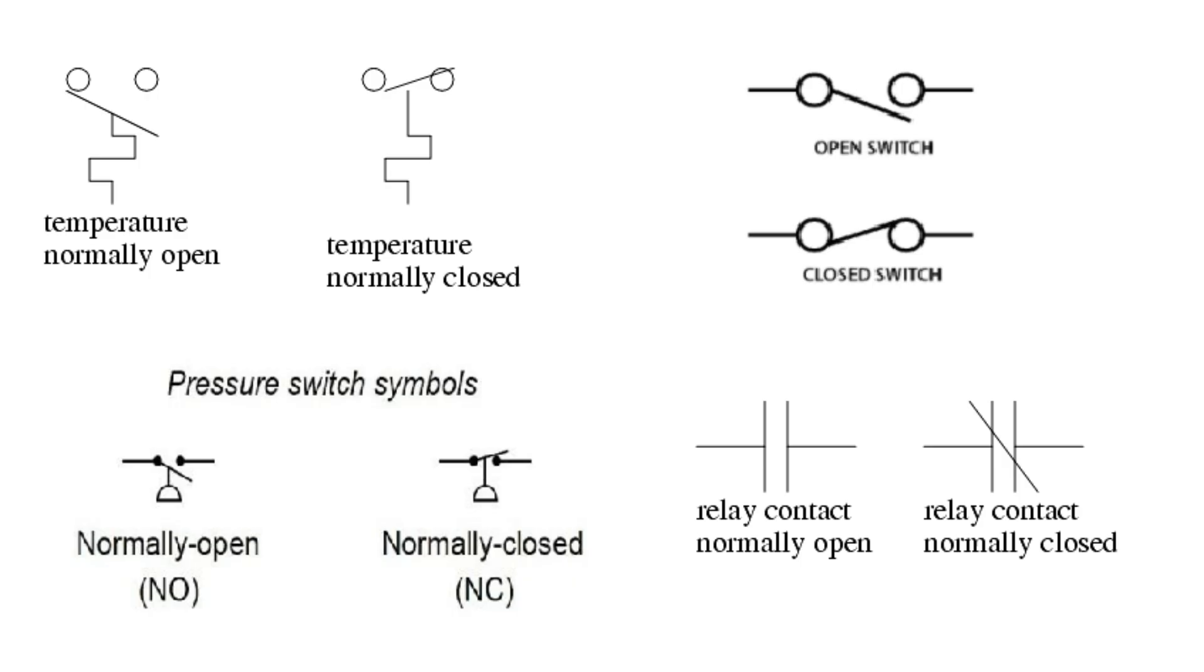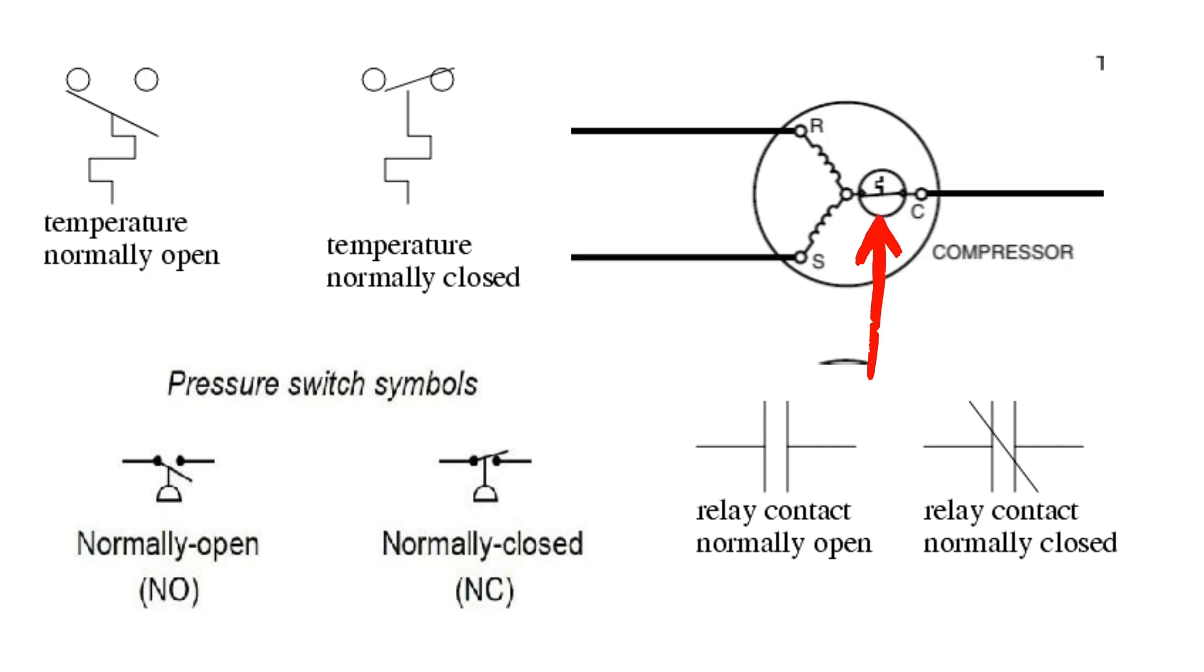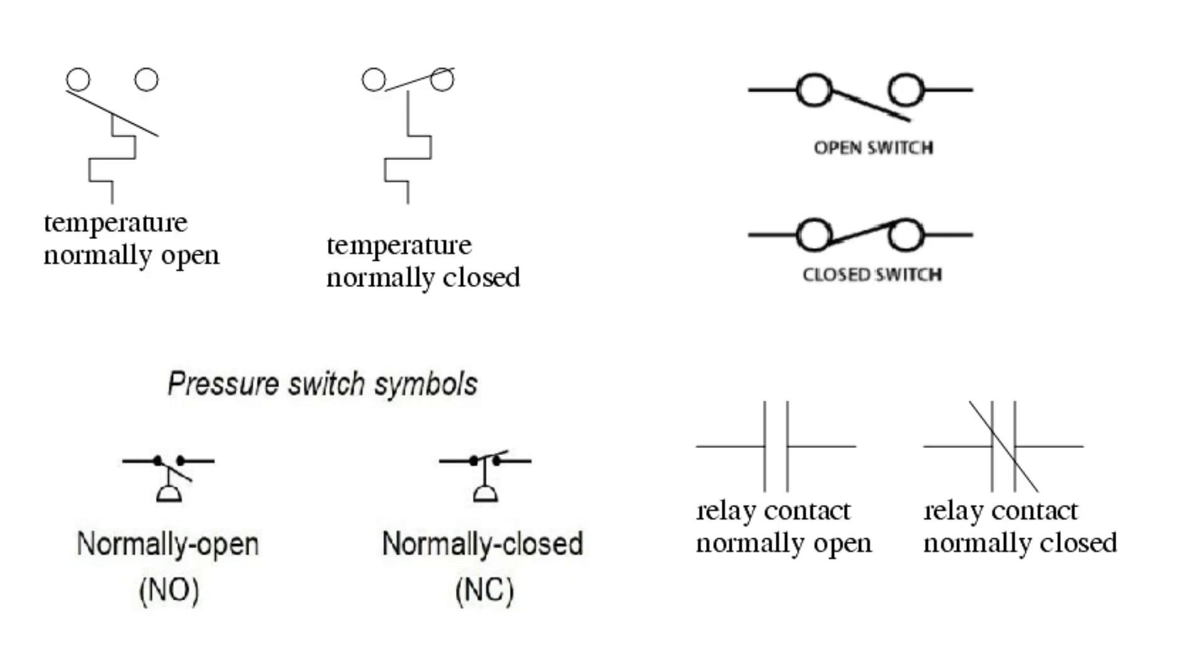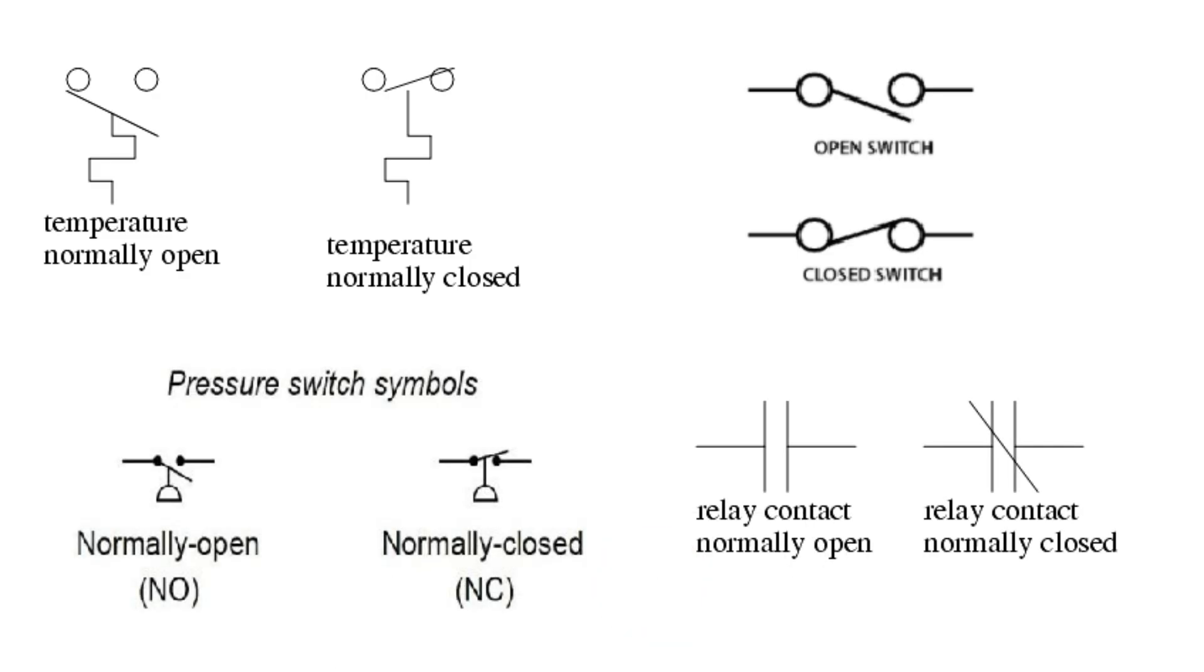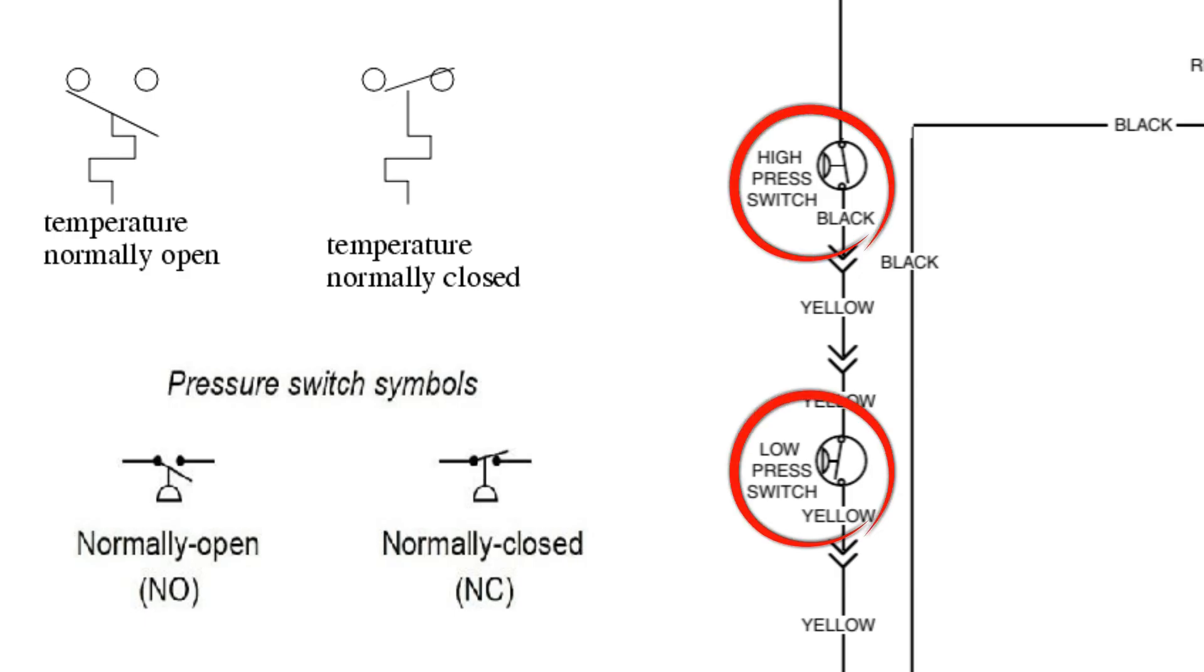So here we have typical switching symbols you're going to see very often on HVAC schematics. To the upper left here, we have temperature switches showing the normally open and normally closed state. This is something you're going to see in the compressor, such as the thermal overload switch. Up to the right, we have an open and closed switch like a light switch on our light bulb diagram. To the lower left here, we have pressure switches. You will find these on condensing units quite often.